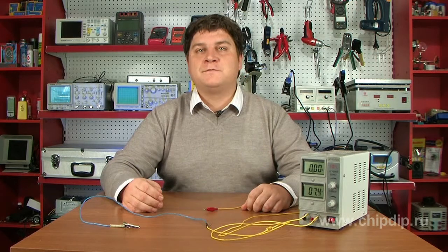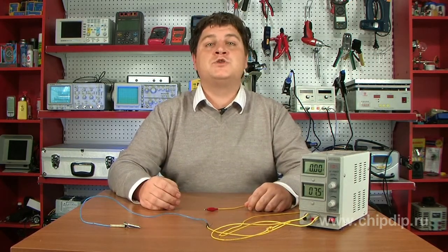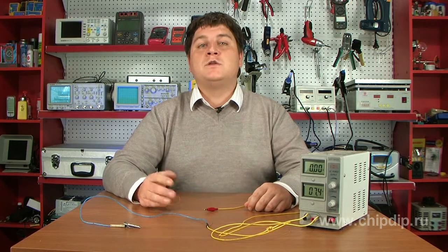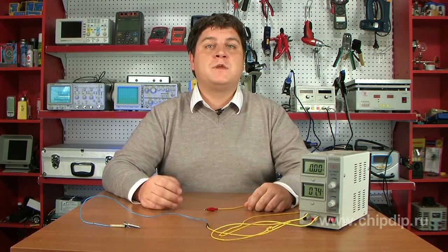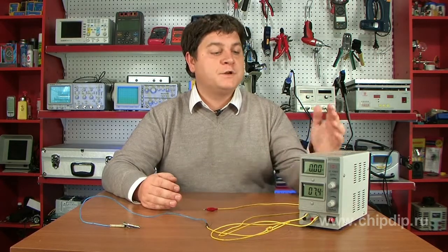As a result, depending on the condenser's capacity, we get a potential of approximately 100 volts on the device frame relative to the mass and neutral mains. Under certain circumstances, this increases the hazard of electrical shock when touching the electronic device body.